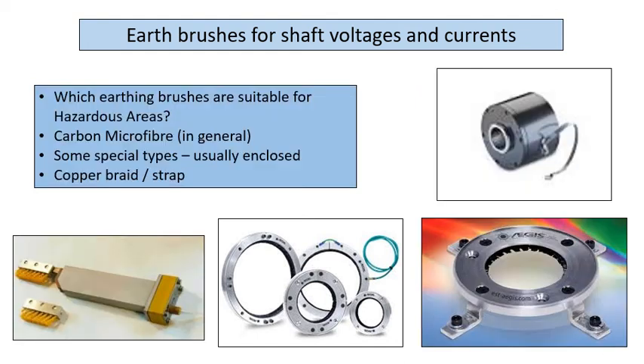I thought the relevant question is which earthing brushes are suitable for hazardous areas, and normal carbon brush, whether it's silver graphite or whatever, is not. The ones that are, in general, are the carbon microfiber. I think you still have to get them tested and approved. The SAIEE is as well. Incidentally, this was what was fitted on the SAIEE machine. It almost looks like a speed encoder, and it has a brush inside it. So that's how they get around the EX requirement. The part that I found interesting was that it had run for 7 years without any issues, even though you're actually shorting out your current path, because it was fitted on the non-drive end. Anyway, it functioned when we tested it, but that's one option.